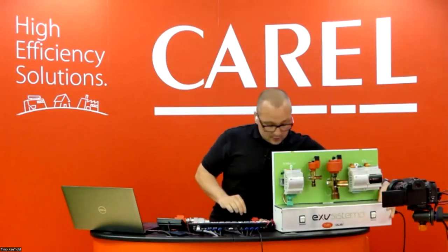Got a question here: do the EEVs close completely when no refrigeration is needed, or is a solenoid needed before in the liquid line? Perfect question, I love this one. The EEV closes completely, so you don't need a solenoid valve, and you should avoid having one if this valve really closes completely. I can show this as well.